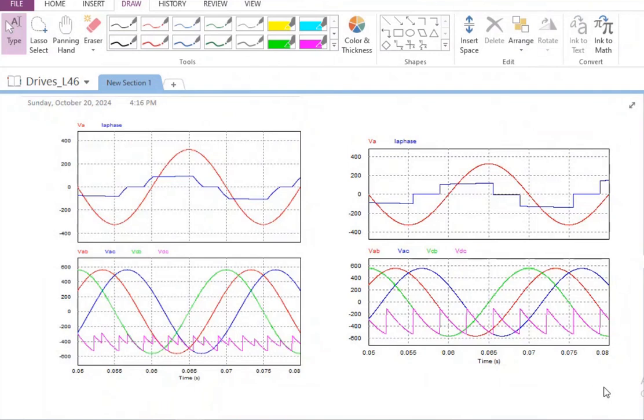Just wanted to give a little bit of clarification regarding the waveforms we get during overlap, especially in an LCI-fed synchronous motor drive. You can see this is without any commutation overlap, especially when the power is flowing from the DC link into the synchronous motor. So this is the A phase voltage waveform, and this is the current waveform.